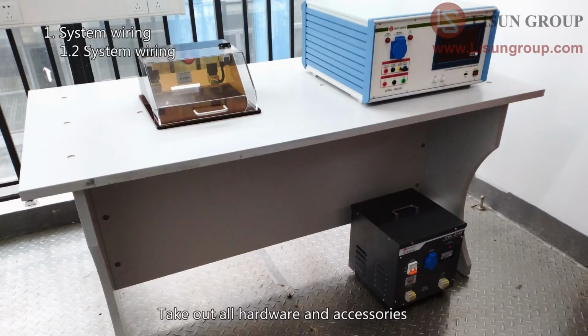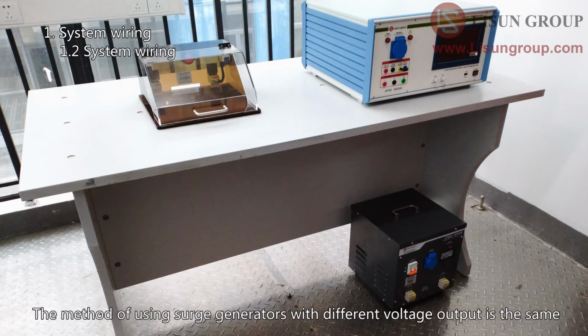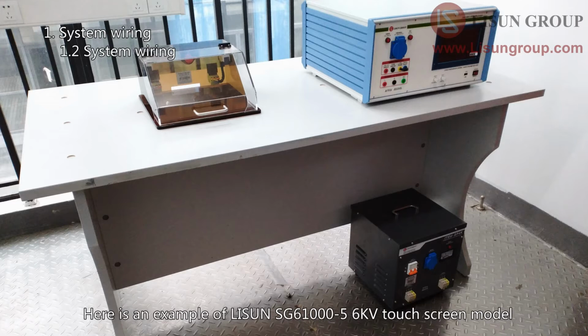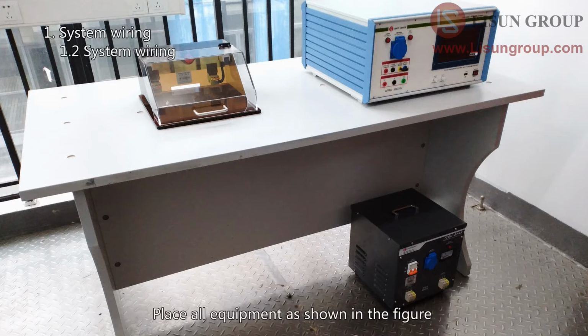Take out all hardware and accessories. The surge generator system does not need to be installed, and only needs wire connection. The method of using surge generators with different voltage output is the same. Here is an example of the LISUN SG61000-5 6 kV touchscreen model.